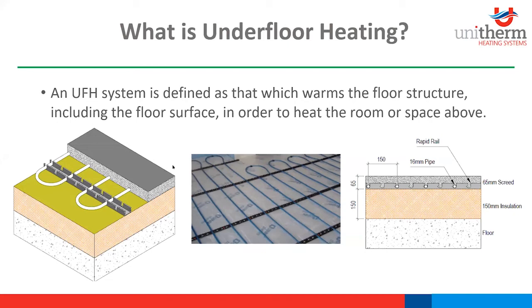Pipe tracking is used, or rapid rail as we call it. That's clipped down, and that accommodates the array of pipes at 150 mil centers. Sand and cement screed is then poured on top to create a thermal mass. So usually your sand and cement screed there is 75 mil for ground floor. The liquid screed is generally 60 mil. But just for your thermal mass in your floor, 75 mil sand and cement is standard.